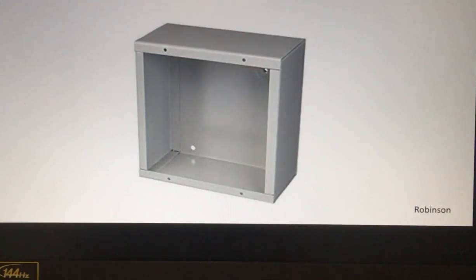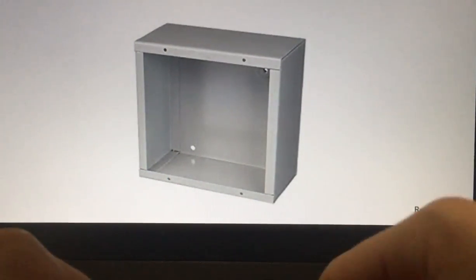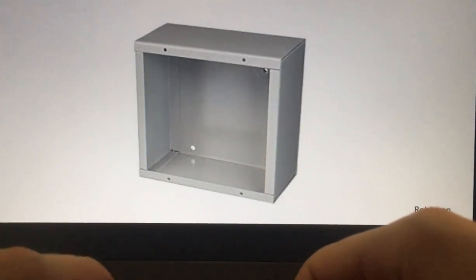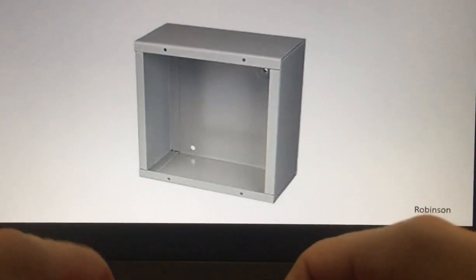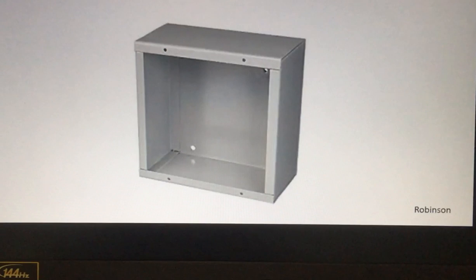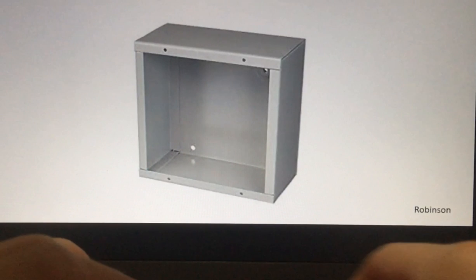The reason for that is when you're doing conduit bending, you can't have more than 360 degrees between pull points, which is four 90s, because you're pretty much just pulling around a big circle. And when I was teaching conduit bending, I always stressed to the students that regardless of what you're doing, as soon as you hit 270 degrees, put in a pull box or some type of pull point.